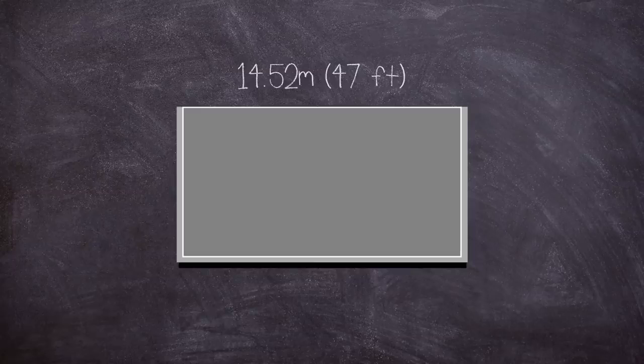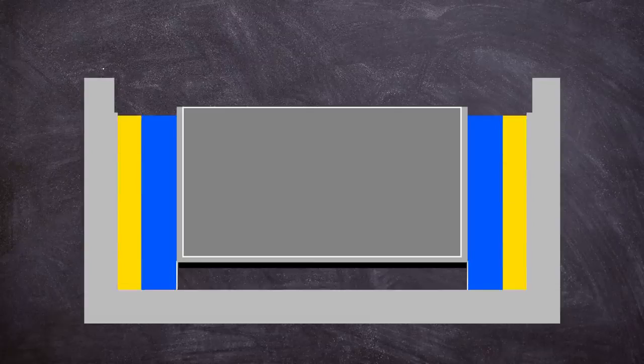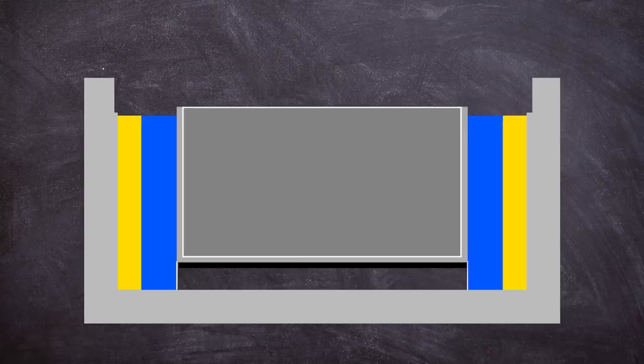The RBMK had a very large core region consisting of a height of 7 meters and a diameter of 11.8 meters which was mounted in a steel cylinder that was placed on top of a biological shield. The steel cylinder was 16 millimeters thick and had a diameter of 14.52 meters by a height of 9.75 meters dug into the floor of the reactor building. Inside a reinforced concrete lined pit between the steel wall and the concrete lining, a water tank was placed followed by a sand packing. Below the bottom biological shield there were several basements used for pipework for the reactor core cooling loops.